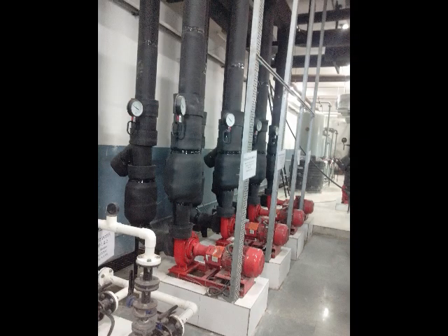These are 4 primary pumps. As per load, the number of pumps running can be 1 or 2 or 3 at a time. These pumps take return water from the AHUs, TFAs, CSUs, FCUs, high wall units and cassette units and feed it to the evaporator. A flow switch is connected in the line, which is a safety device. If the flow is there, then the AC will get started. Each pump has pressure gauges for monitoring inlet pressure and outlet pressure.